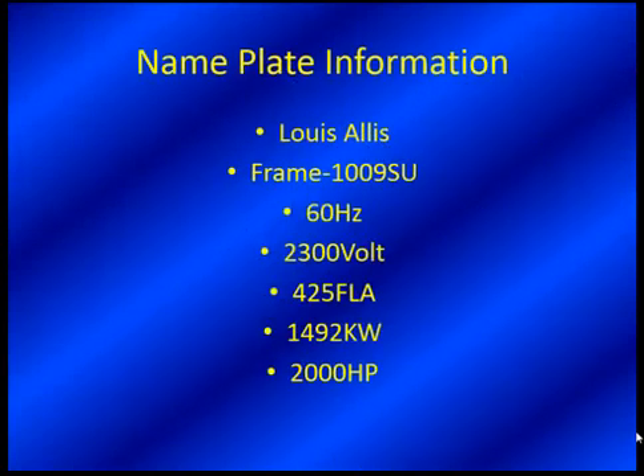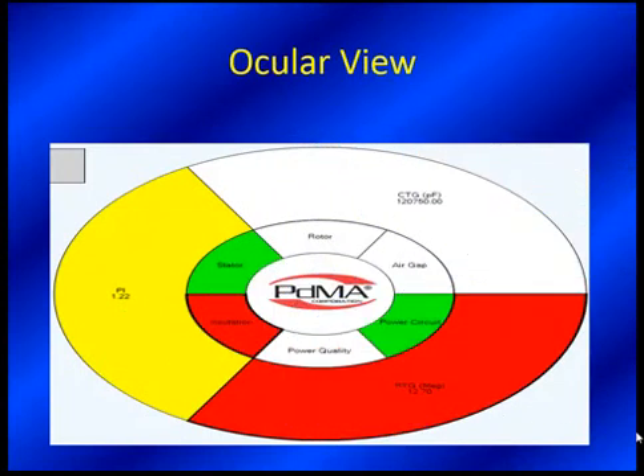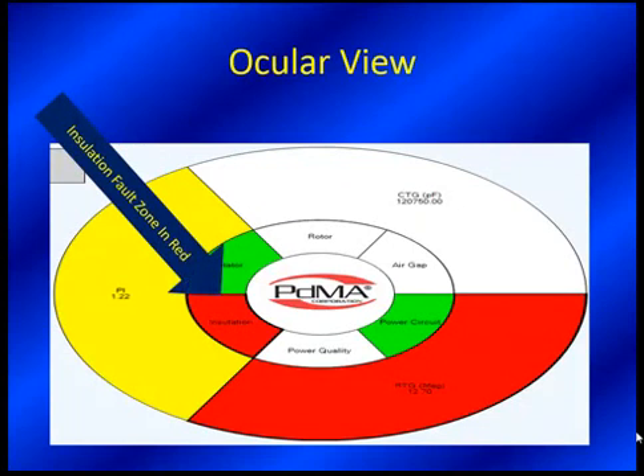This is the motor size. You can see it's a 2.3 kV motor and 2,000 horsepower — a good size motor and certainly one that you don't want water running through. You don't want water in that insulation system. Our MCEGold 3.0 is recently released, and it really takes our six fault zones and puts them into a circular or ocular view to make it a little easier for the technician to see what's going on. The ocular fault zone is very interactive and has been one of the key interest points for people looking at the new software.